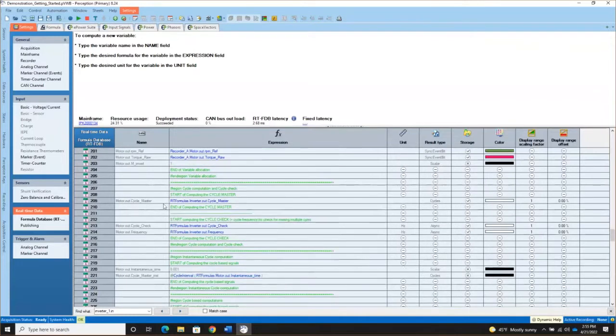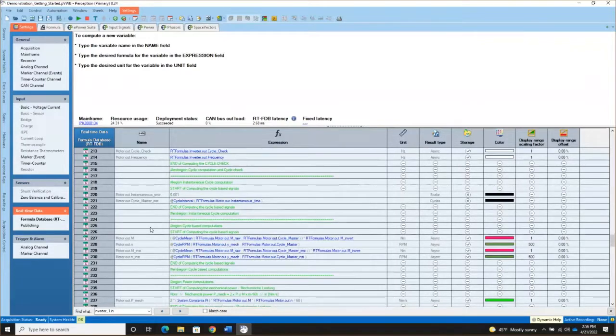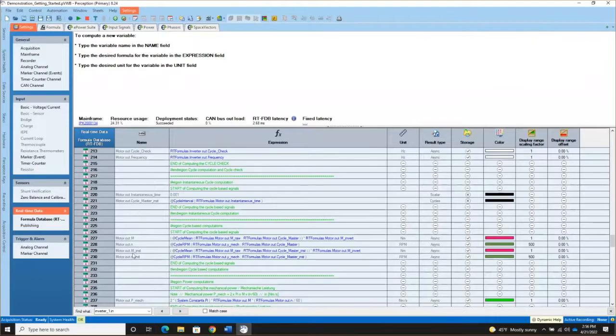We again have our cycle master of the torque tied to the inverter. On the torque side, we always create two different cycle masters. We want to know the torque over the electrical cycle for efficiency calculations, but there are also interesting things happening on the torque signal on a much faster time scale. So we create a second cycle master — the instantaneous cycle master for torque and speed — which is a timed cycle of one millisecond. Every one millisecond we determine torque and speed. These variables are M_instantaneous and N_instantaneous. When you see M (torque) and N (speed) without a suffix, that's over the electrical cycle; the instantaneous is over that one millisecond.